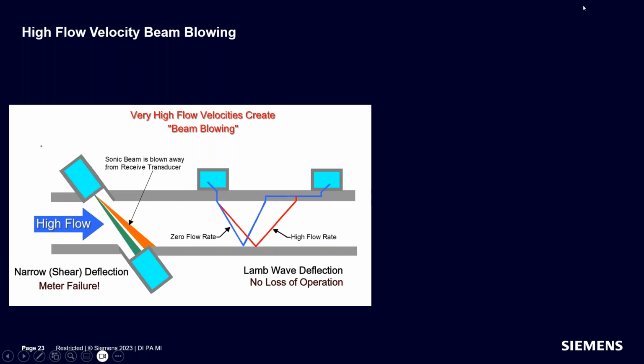And then the other aspect of gas is that the flow velocity is much higher than it is for liquid. So what happens is the beam actually gets blown away from the receive transducer. If you look at a wetted type flow meter, there's a potential to lose the signal altogether because the beam is collimated, shooting from one transducer to the other. And when you have a high velocity flow, it's pushing the beam away. And if it pushes it far enough away, you'll lose it and the meter just fails. With a wide beam transducer, although the beam still gets pushed down the pipe, it still arrives at the receive transducer because there's so much energy over a wide area of the pipe that the signal is not lost and the meter is able to maintain operation.